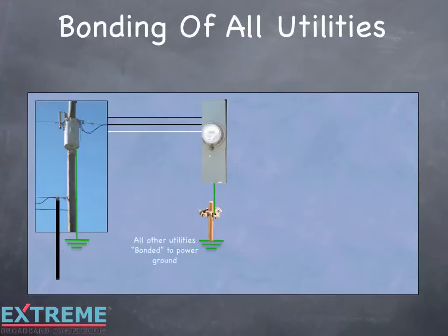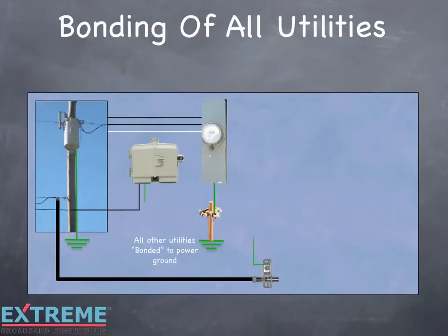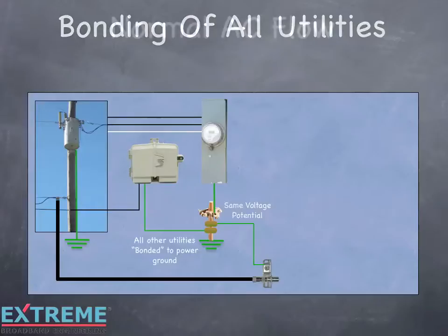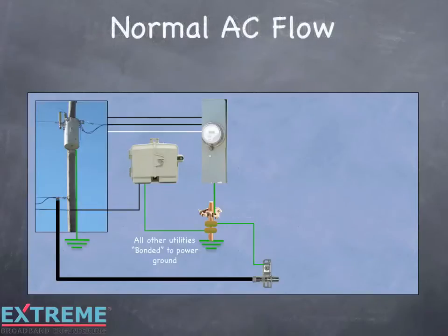All other utilities, such as cable and phone, bond to the power ground using their own separate attachment to the power ground. The outer shield of the coaxial cable is now bonded to the power ground through the bonding block and is at the same voltage potential. Bonding keeps all the utilities at the same voltage potential as power. The power meter is connected to the circuit breaker panel, which establishes individual power circuits within the home.